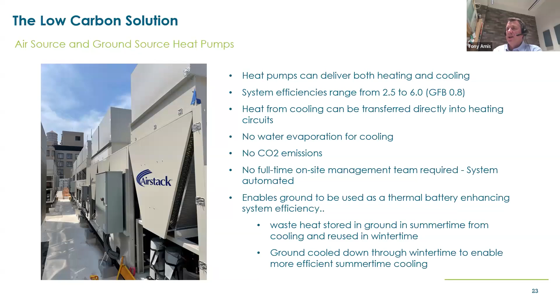So you're getting rid of that evaporation of 4.8 million gallons of water a year, no CO2 emissions. With the kind of cooling systems we used to see, there used to be full-time management on site required. With these kind of systems, you just need somebody to manage it. It's pretty much self-automated, and the system Cerys showed you would probably send an alarm to the maintenance team if there were issues, but they generally run themselves. They probably need a little bit of monitoring over the first 18 months, but generally they are pretty efficient at running themselves.